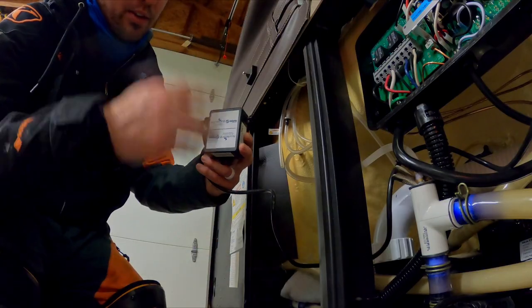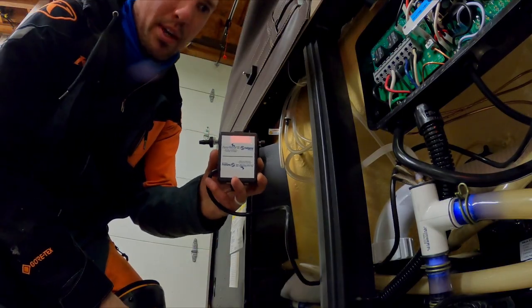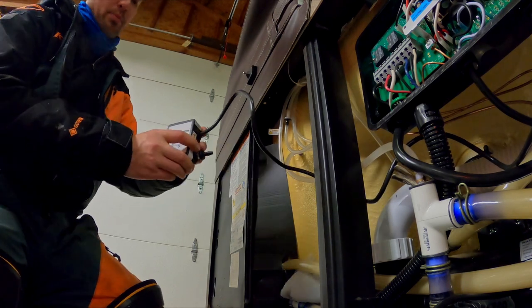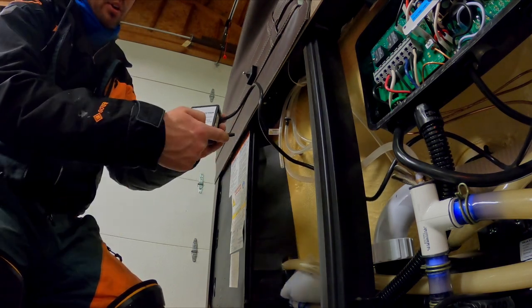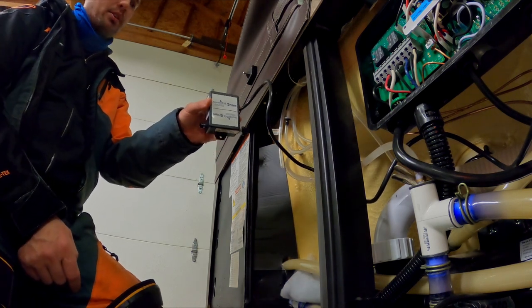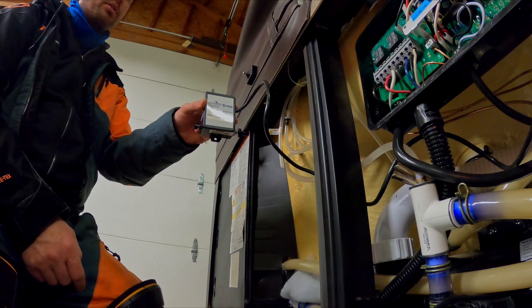Then it would fill up the box, shorting something out before it makes it through here and drips out. Then you know we're going to cause problems with the rest of the hot tub system, tripping breakers and whatnot. It's better if we mount the box this way. If the water does make it in here, it's likely to just drip back out again before it damages anything or trips any breakers.